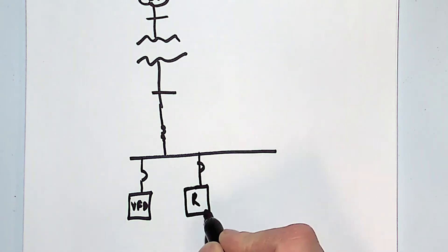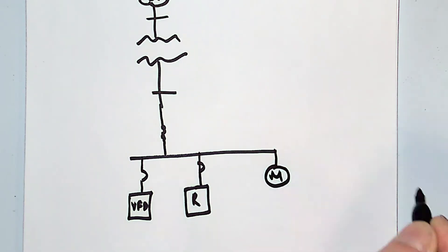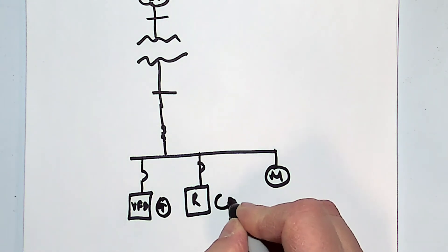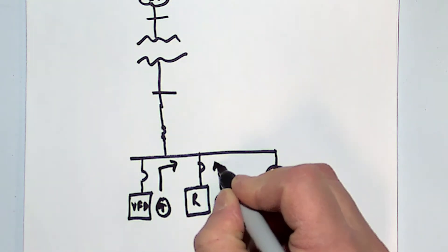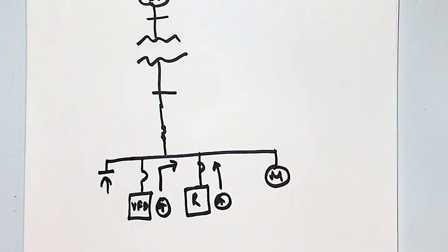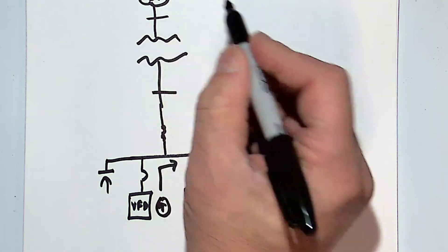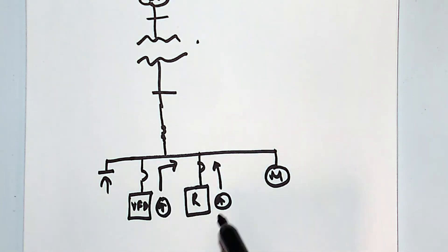As we model those throughout the system — and maybe we also have some linear loads like motors — we're going to identify these harmonic sources and create what we call constant current sources and push that current back out on the system. And if we have capacitors on the system, we're going to model those capacitors and see how they interact with harmonic loads. Mostly what we're doing is creating an impedance model — there's a resistance and reactance with the utility, with the transformer, with the cable, with the busway, with the cables.